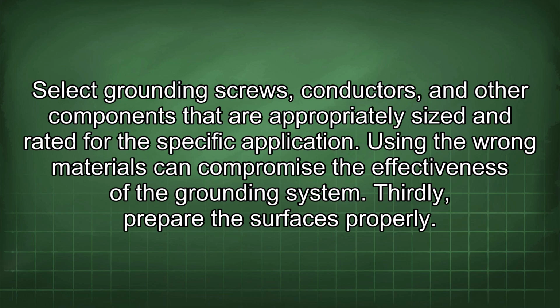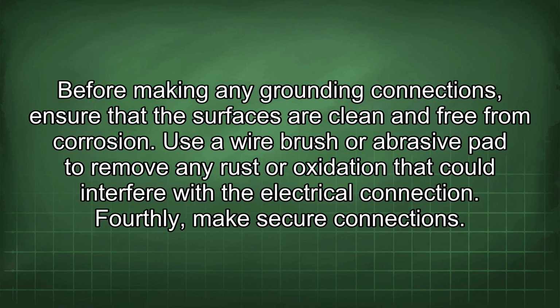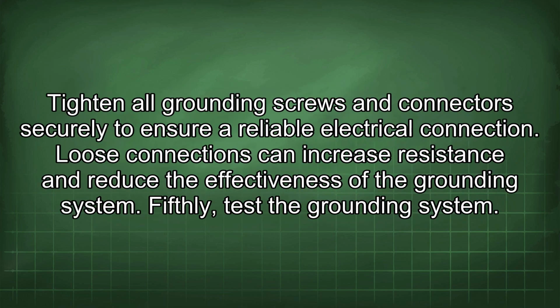Thirdly, prepare the surfaces properly. Before making any grounding connections, ensure that the surfaces are clean and free from corrosion. Use a wire brush or abrasive pad to remove any rust or oxidation that could interfere with the electrical connection. Fourthly, make secure connections. Tighten all grounding screws and connectors securely to ensure a reliable electrical connection. Loose connections can increase resistance and reduce the effectiveness of the grounding system.